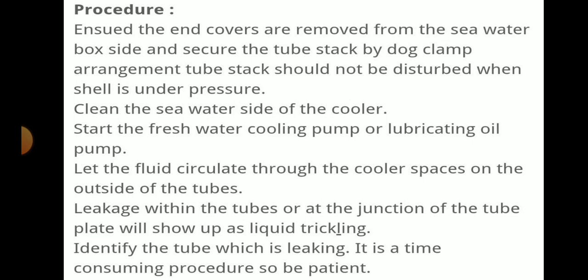Leakage within the tube or at the junction of the tube plate will show up as liquid trickling. So identify the tube which is leaking. It is a time consuming procedure, so we have to be patient.